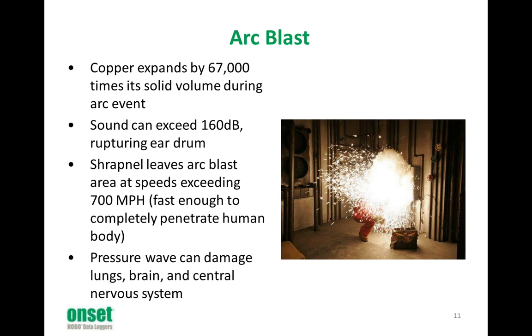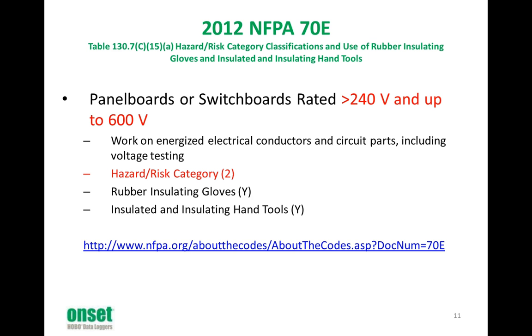A few other notes. Copper expands by 67,000 times its solid volume during an event if something shorts out. Sound can exceed 160 decibels, rupturing the eardrum. Shrapnel leaves the arc blast area at speeds exceeding 700 miles an hour, fast enough to completely penetrate the body. Pressure wave can damage lungs, brain, and central nervous system.